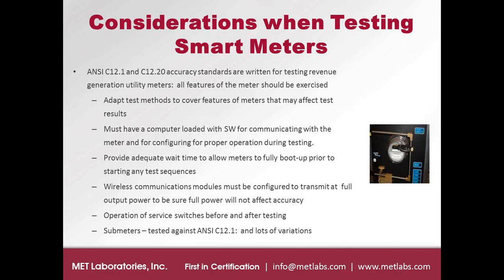And even though the standard is written really for the revenue generation utility type meters, the public service commissions tend to, more often than not, have criteria for sub-meters that defaults back to testing against the provisions of ANSI C12. So really, sub-meters are subjected to these tests.